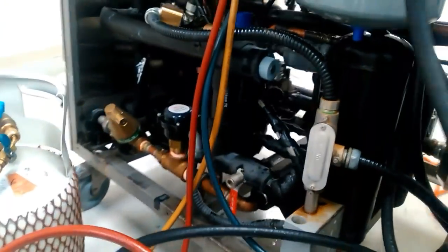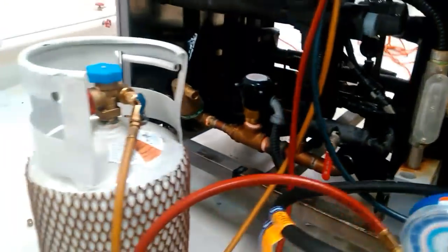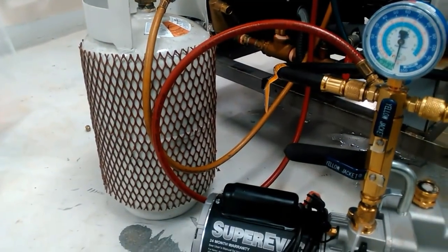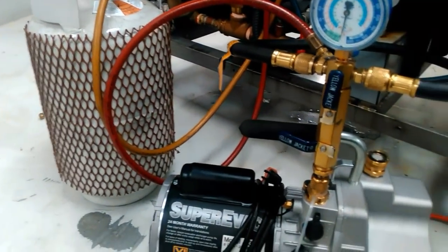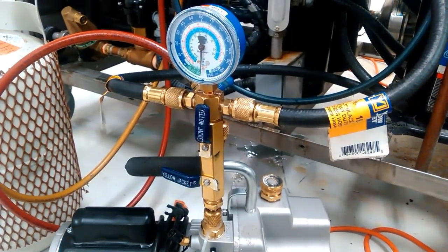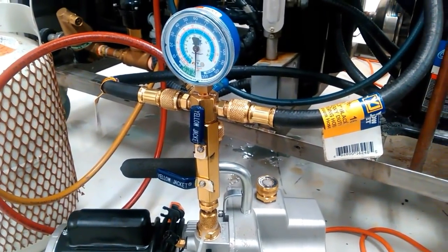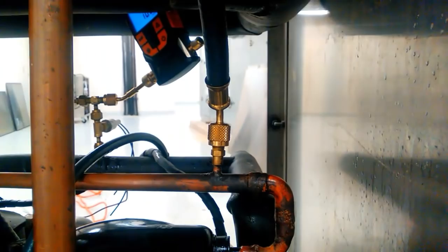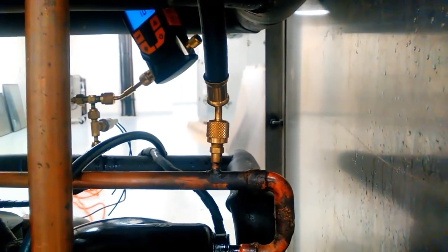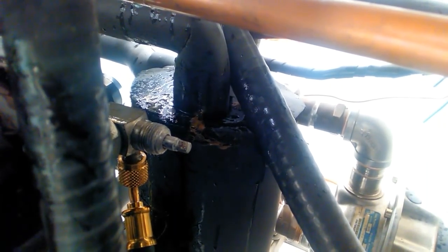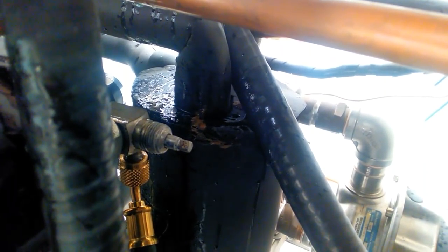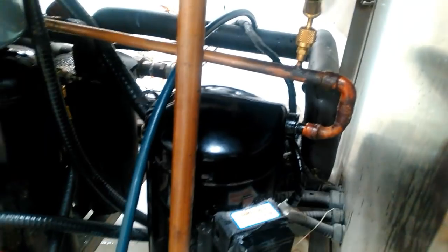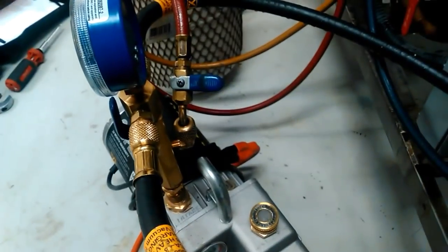Now if you're lucky and you weigh the charge in, you might get the whole charge in before you have to remove your hoses. If you don't, don't worry about it because you've got a holding charge in there now. All you've got to do is remove your hoses. If you have a core removal tool there, you put your core back in. Before you remove this hose on the king valve, you'd have to close that valve off. Remove your hose, put your charging hose back on, and open it up again. That's how you get your holding charge in without taking your hoses off.